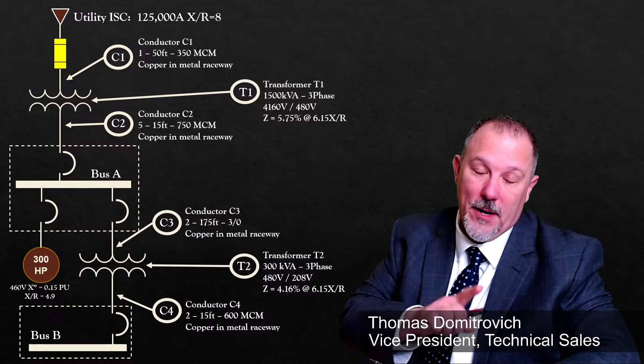Here's your homework. Remember, we created the impedance diagram - this is our impedance diagram. We're going to continue to use this model, even though we're making changes in our other example, because we've already calculated all of our per unit impedance values. Start with this, and figure out what the impedance diagram is to calculate the ground fault current at bus A and bus B.